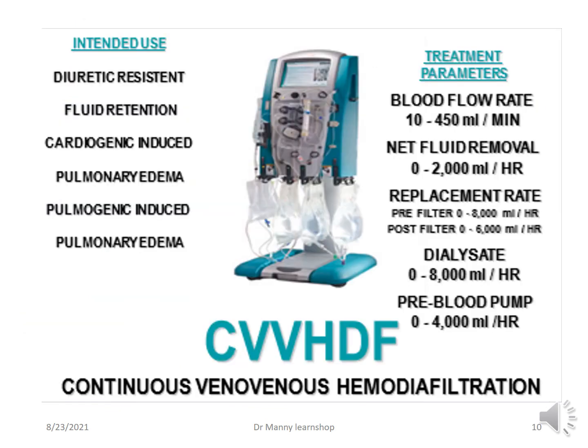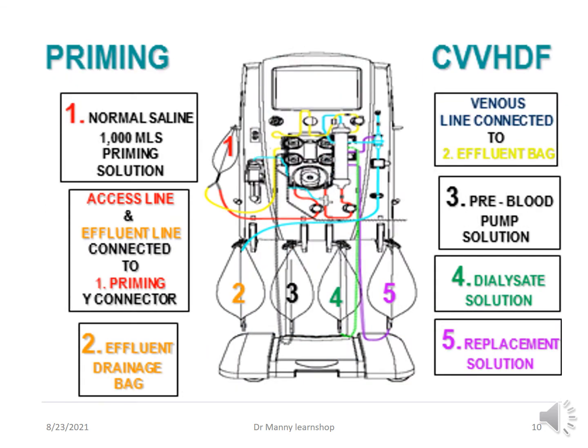CVVHDF, continuous veno-venous hemodiafiltration, does everything now. It does hemofiltration, it does dialysis. Intended use is essentially the same, but it offers you everything, and the whole circuit is primed. So during priming, normal saline primes the circuit. Access and effluent line are connected to the priming Y connector, as with all the other therapies, and they all drain the fluid, air, any sterilising contaminants into the effluent bag. Typically, 2000 mils is used as priming solution in most priming setups.